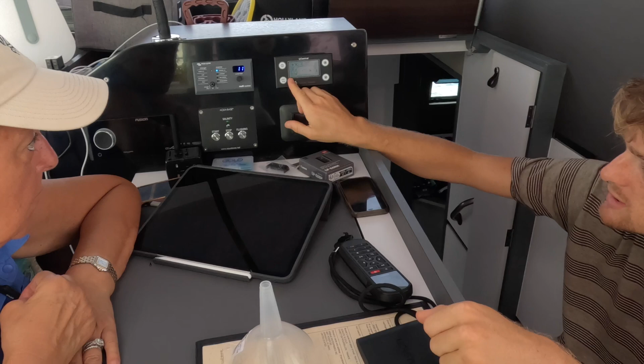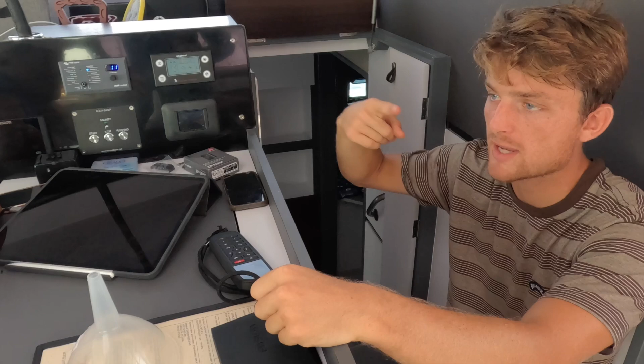When you switch off the genset from here or from the main screen, it's important to wait for the cooling down phase, which is always 5 minutes. This matters because when the genset is on, it's charging at 16 kilowatts. When you click start to stop it, it puts the charging number to 0, but the cooling system keeps running. So the genset will run the cooling system without charging for about 5 minutes, and it's important to respect this phase, otherwise you can have trouble with the sensor and everything.